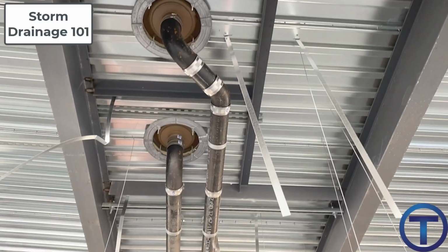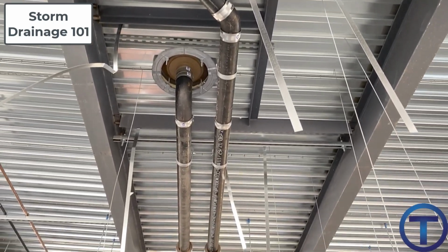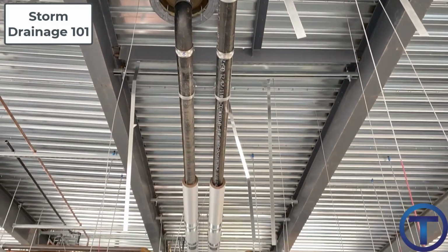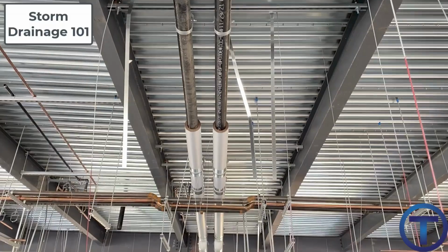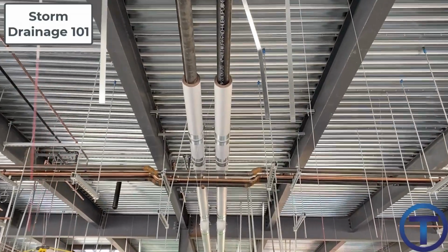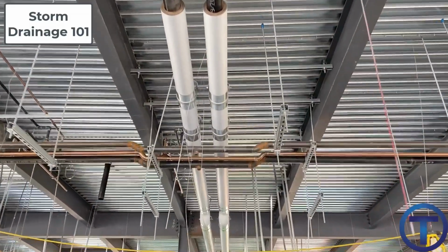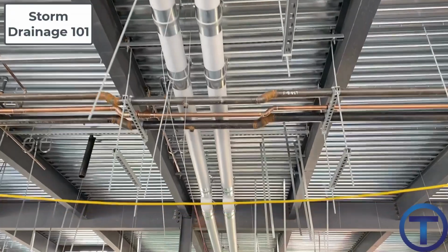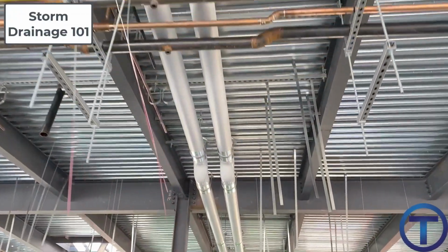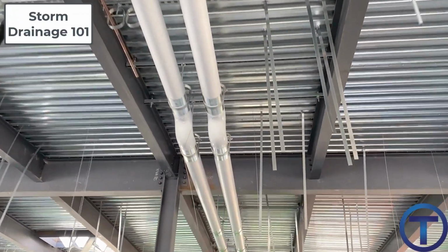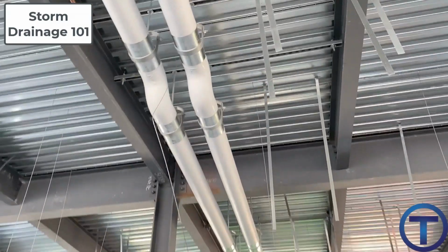Now, roof drains are very often installed with insulation. The insulation is going to do two things for us. One, it's going to keep it a lot quieter. You can hear water moving through pipes in a ceiling, but the insulation is going to muffle that. The second thing the insulation will do is to keep water from condensing on the outside of the pipes.